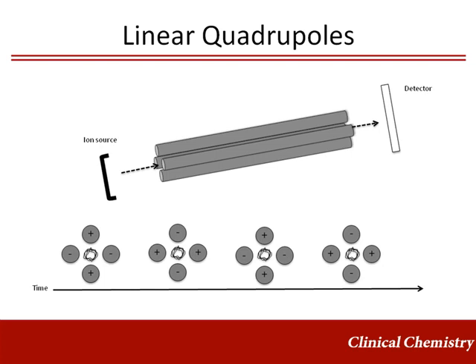Each combination of voltage and frequency will result in some ions traveling through to the detector while others have unstable flight paths and ground out on a rod. How long the mass spectrometer sits at a voltage and frequency combination is called the dwell time, during which only a limited number of ions are successfully reaching the detector. Quadrupoles have limited mass-to-charge range, high sensitivity, high mass accuracy, but a low ion transmission percentage.